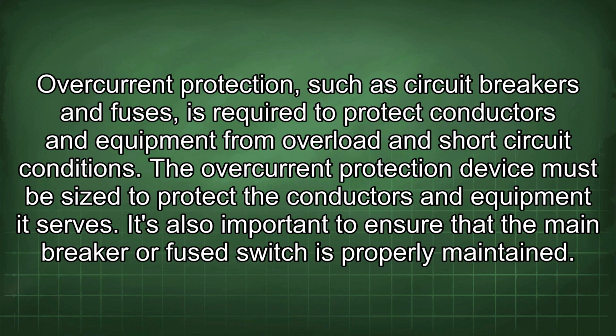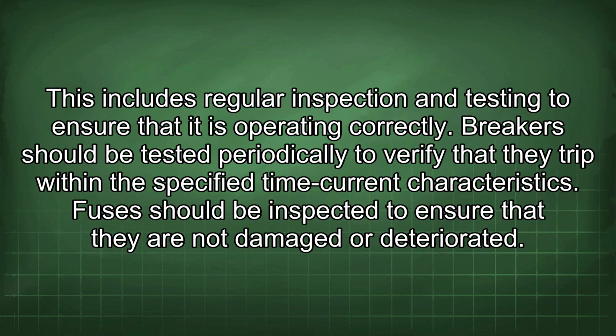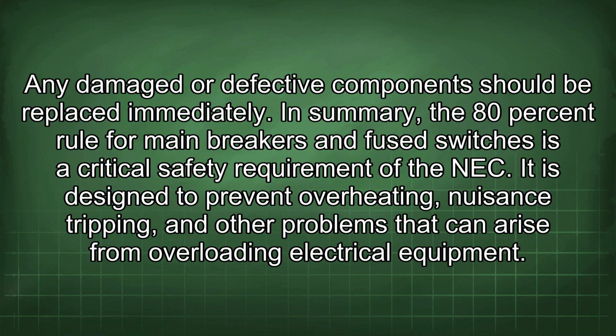It's also important to ensure that the main breaker or fuse switch is properly maintained. This includes regular inspection and testing to ensure that it is operating correctly. Breakers should be tested periodically to verify that they trip within the specified time current characteristics. Fuses should be inspected to ensure that they are not damaged or deteriorated. Any damaged or defective component should be replaced immediately.